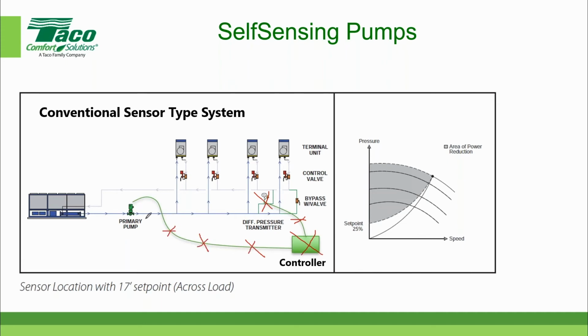All you have is the pump, the motor, the drive. You put that into the system, you power it up, you press the on button, it knows exactly what to do. As the valves open and close, the pump increases and decreases its speed automatically. So that's how we're going to talk about how it accomplishes that. So let's erase some of these lines here and go on to the next slide.